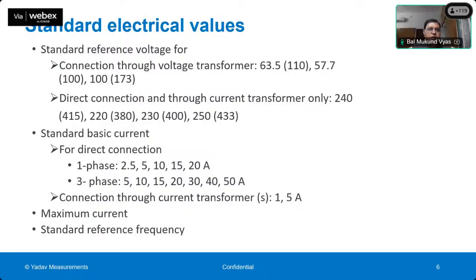Various kinds of standard reference voltages are specified for electricity meters. Depending on the country, they are selected. If a meter is connected through a voltage transformer, which is mostly in industry or at grid level, then 63.5 volt is mostly used in our country. And if the meter is to be direct connected, like in our houses, or through a current transformer also, then it has to be 240 volt, which is mostly used in our country. In some countries, 220 volt, 230 volt, or 240 volts is used. So different voltages are specified.